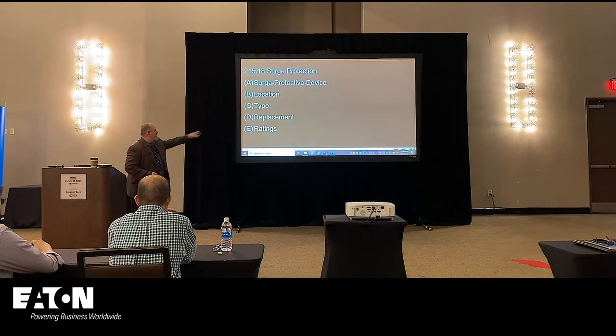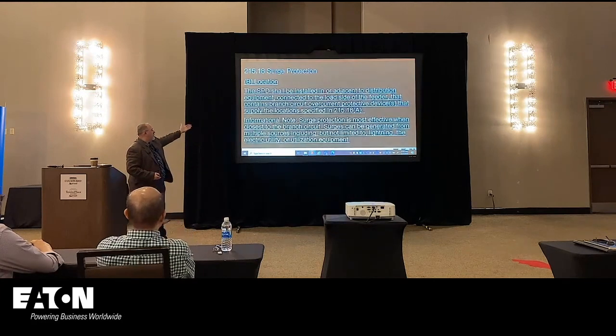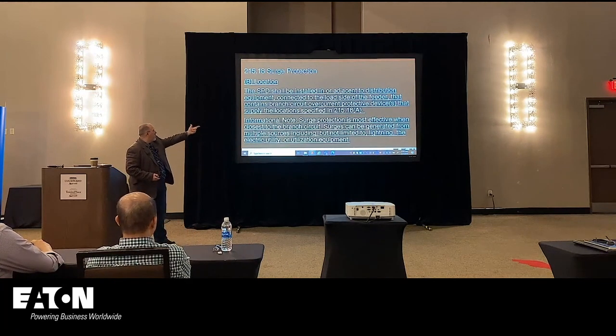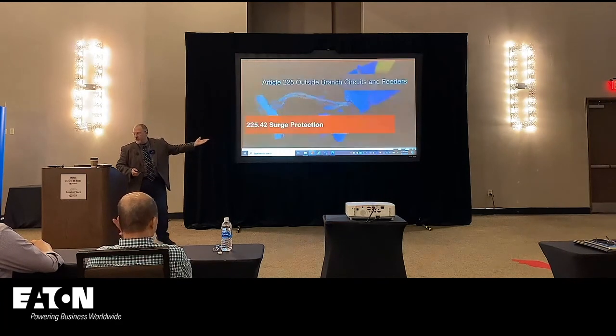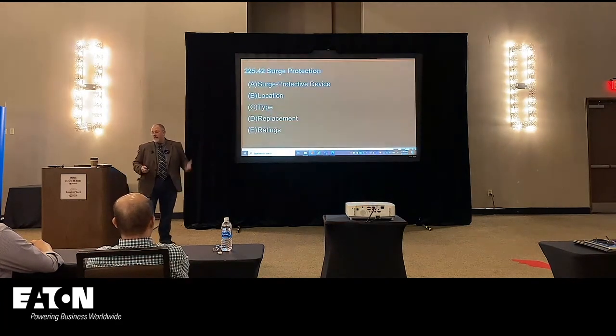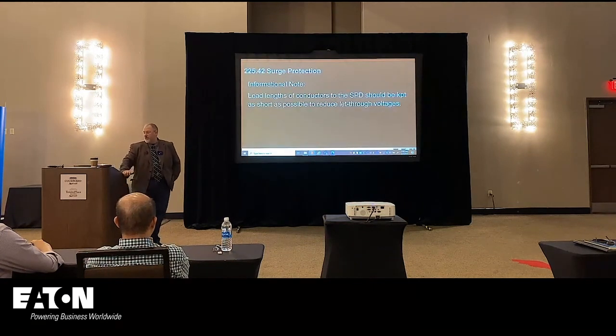We did the same thing in 210.8. You'll see the same structure, same language: load side of the feeder, it contains a branch circuit. So this is basically the same language that we saw in 225 and in 230. My only reason, there's the language I got in for the lead lengths. I argued that one. I argued very passionately at the table too, but it was online. So this cycle was all virtual. There's only so much emphasis you can put when you're just a voice on the other side of the phone. All right, energy management systems.